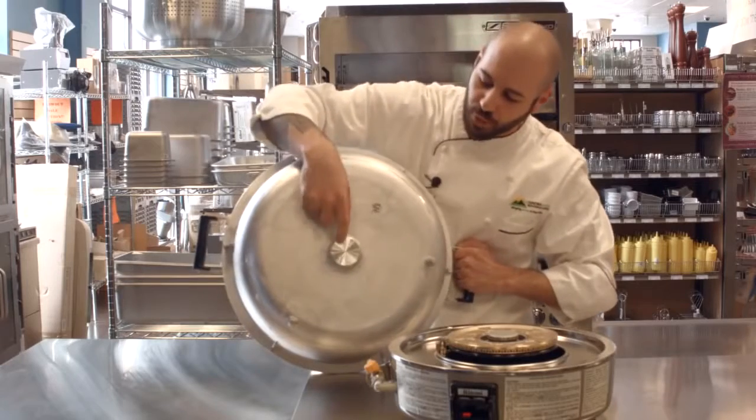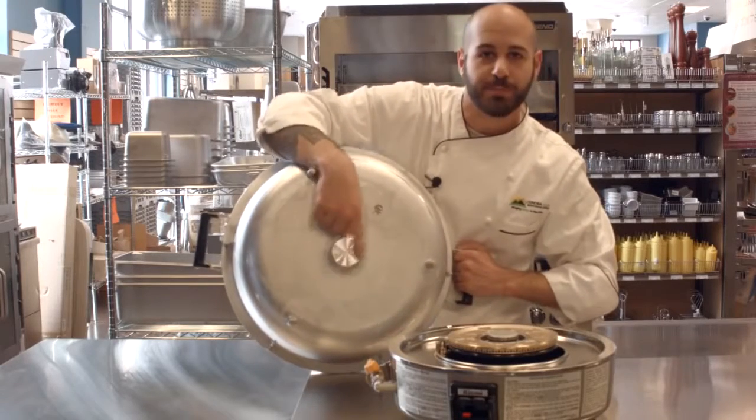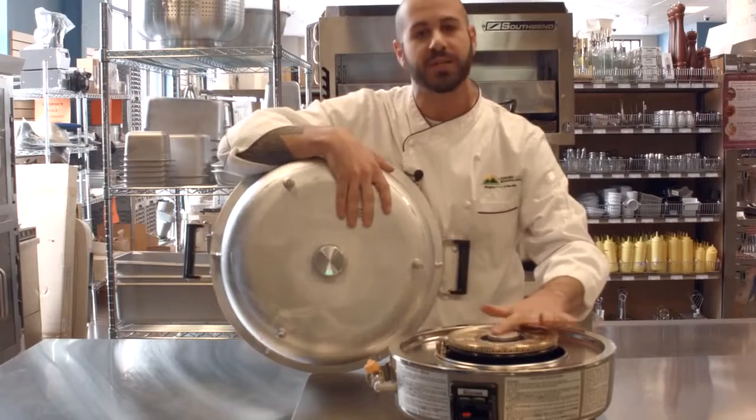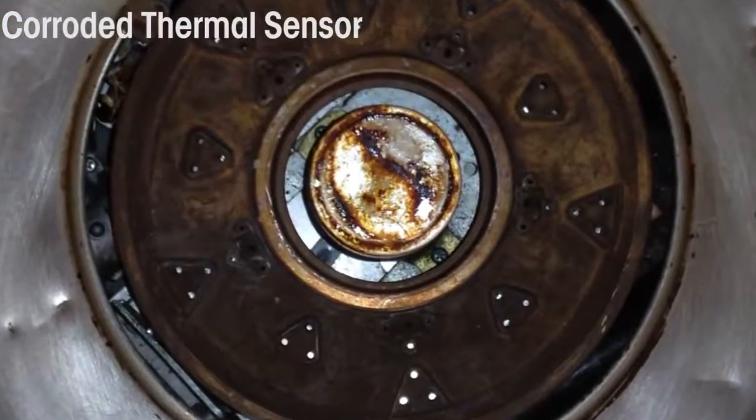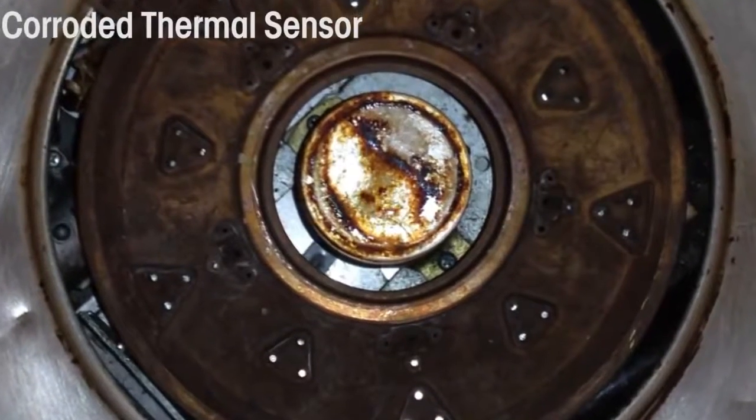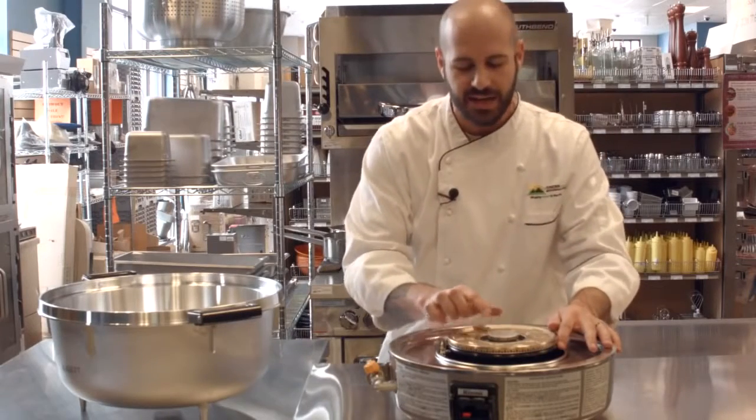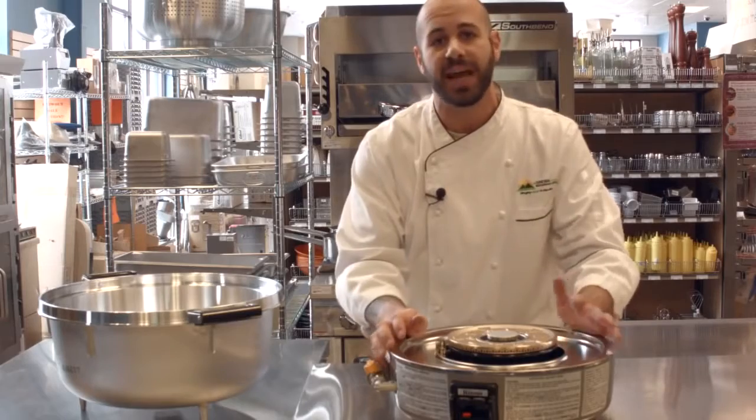Always be sure, first and foremost, that this surface is spick and span clean, as well as the top of your thermal sensor itself. From there, if you see any type of wear and tear from the daily grind, and it is clean but you see the impression of the magnet inside, that means your thermal sensor needs replacing anyway.